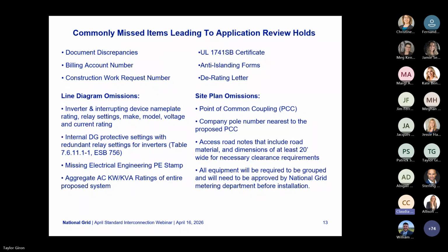On the other side, for site plans, mistakes or omissions include a missing PCC, the point of common coupling, or POI. We may also have missing notes about the access road needing to be 20 feet so that enough clearance is provided, the company pole number nearest to the proposed PCC, and that all equipment will be required to be grouped. The note about ESB 750 and ESB 756 regarding metering and interrupting devices such as disconnects needs to be there.